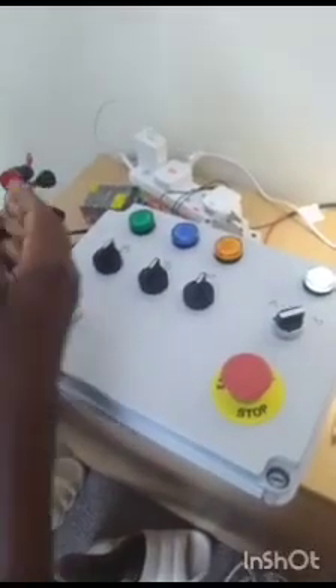I want to operate the mode. For example, the machine has an issue, and the operator wants to check what the issue is. Is it the mode? Is it the stretcher? Is it the blowing section that has an issue? It goes to the manual mode, then operates each section individually to see if it's a mechanical fault, an electrical fault, the coil, and so on.